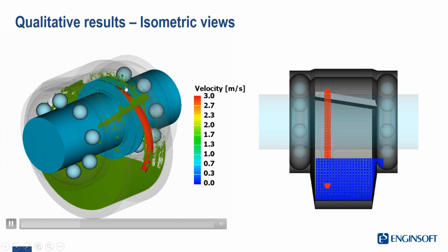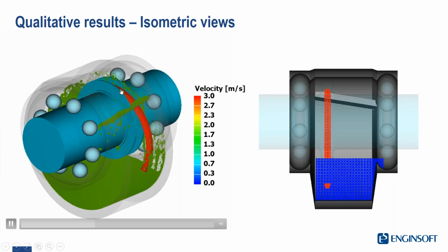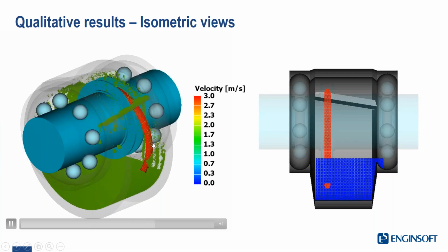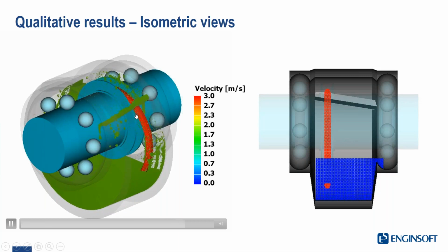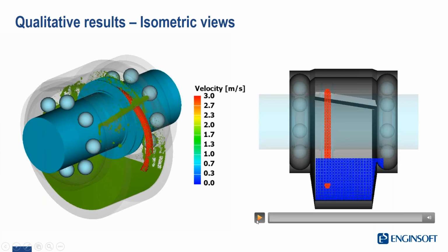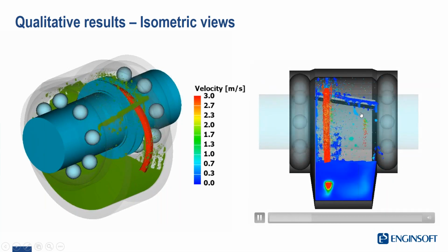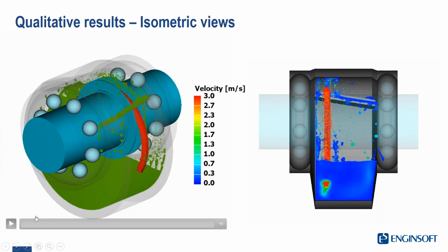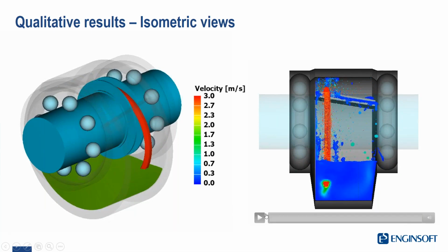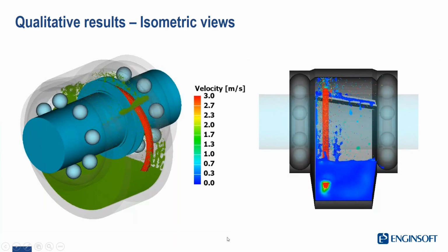As you can see, the ring is interacting with the shaft, is moving due to this interaction and the grip between the two, and oil flows because of the interaction between the ring and itself, and goes to the channel, only one channel. And as you can see in the other animation, we also do see some oil dripping down in the bearings area. So exactly as expected. So I will just replay for a couple of seconds the two videos if you didn't catch every detail.